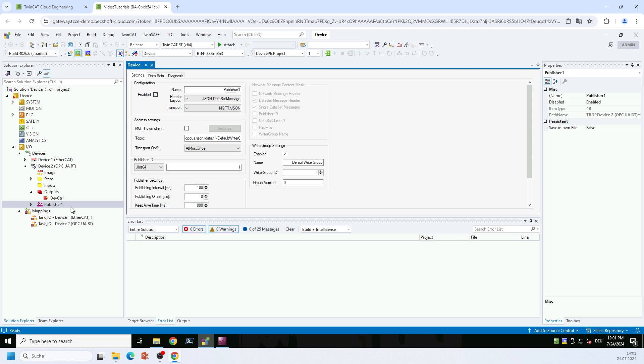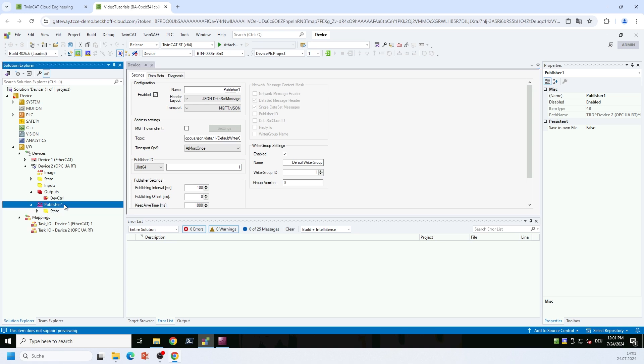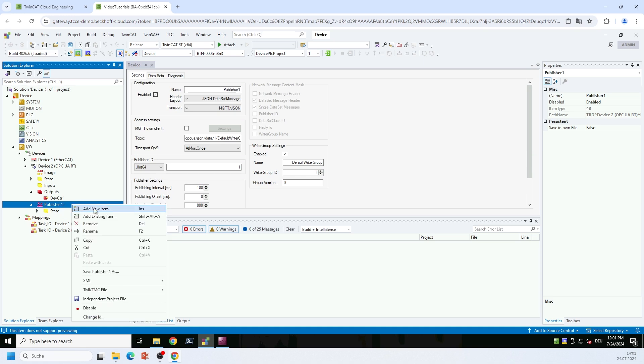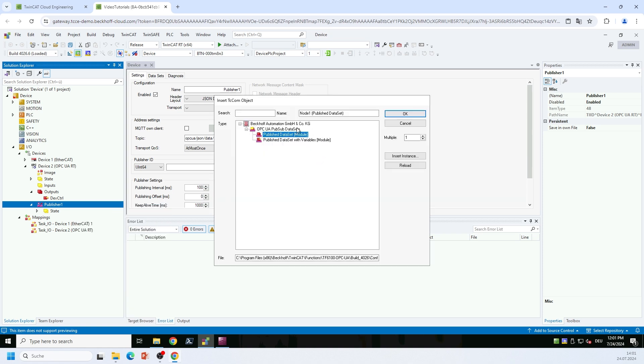And after we have configured this publisher node here, we want to add a data set, and the data set will contain the variables that we would like to transport. So I right-click the publisher node, I select add new item, and I then have the option to configure two different kinds of data sets. The first one is a data set without variables, which means that you can add variables for example via the target browser. And the second one is a data set with variables, and this data set will then contain all the variables on the process image here of the IO device, and then you need to do a link to, for example, PLC variables. But we will stay with the first option, publish our data set without variables.